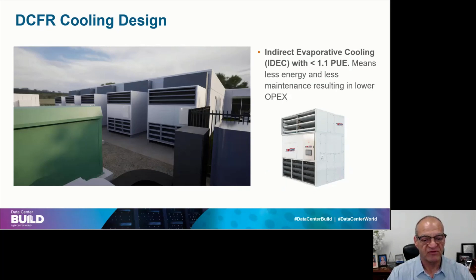So for the cooling design, let's go another way, to achieve very low operating cost. Again, I can operate these, this is from XCool, who was at the show as well, up to about 50 kilowatts per rack easily in this environment. What I love about this is it has multiple cooling modes all baked into one box, and I just need to parallel them for the level of redundancy I want to operate at. So why the IDEC?